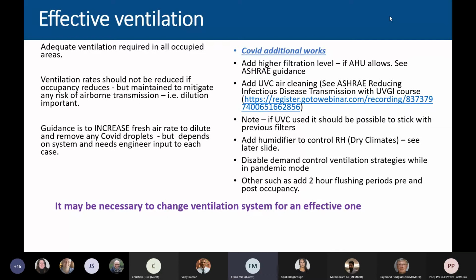So certainly the advice at the moment is ventilation rates should not be reduced if occupancy reduces. We need to maintain good rates that mitigate any risk of airborne transmission. In other words, it maintains that dilution rate with whatever air change rate we have. We want to increase the fresh air rate if we can. So if there's anything we can do to our systems to get more air through, we should do that.